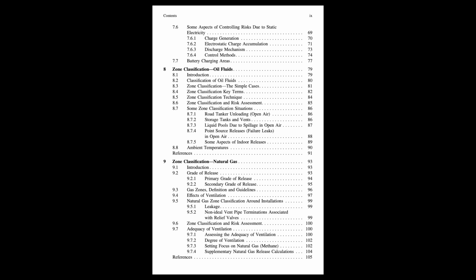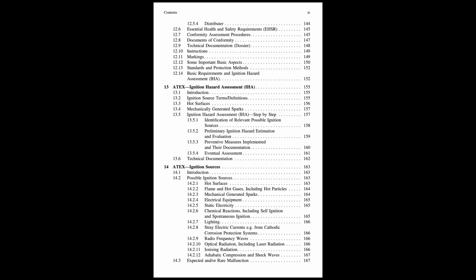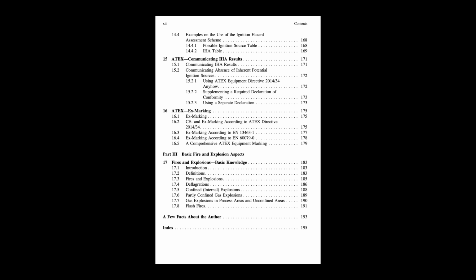Right. And for dusts, it's similar logic, but zones 20, 21, and 22. Zone 20 is where a combustible dust cloud is present continuously, frequently, or for long periods, typically inside process equipment like mills or silos. Zone 21 is where a cloud is likely to occur occasionally during normal operation, like during bag tipping. Zone 22 is where a cloud isn't likely in normal operation, and if it happens, it's infrequent and short-lived, often associated with leaks or dust escaping enclosures.